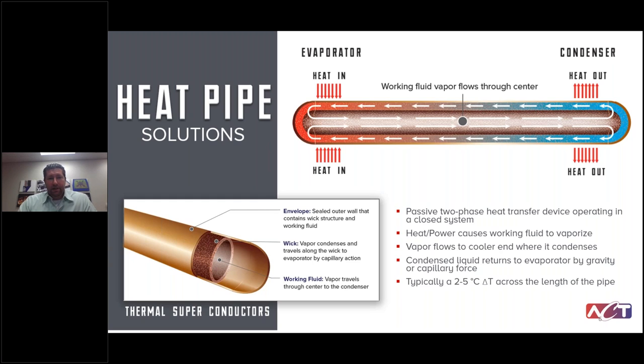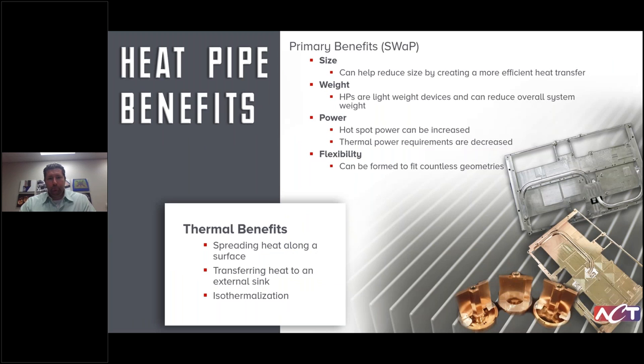That pressure gradient pushes heat from the evaporator to the condenser zone, where it gives up its latent heat, condenses back into a liquid, and is captured within the wick structure. The wick lines the inside diameter and creates a passive capillary force that pumps fluid back from the condenser to the evaporator. The result is no moving parts, a highly reliable system, very high heat transfer coefficients, and typically a two to five degree temperature difference end to end.